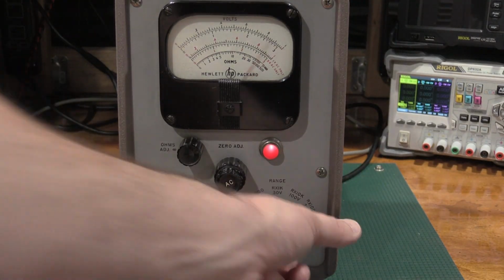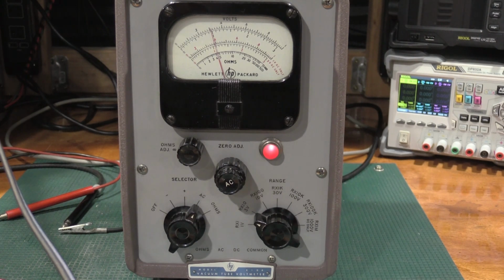Okay, so next we're going to do the 3 volt range for AC. I need to bump the calibrator up to 3 volts, which I have to move this to the 10 volt range to do. And bring this back down because I just slammed the needle. Didn't mean to do that. 3 volts. 997. 999. A little bit more. The range switches on the front of my 5200A are very fiddly, so I don't necessarily care what the range switches are. I'm comparing them to the 7510 and using the 7510 as a transfer standard to bring its accuracy down to the 410B.